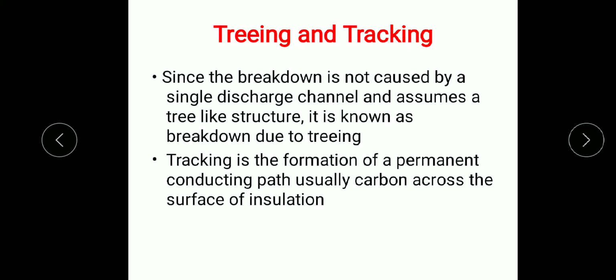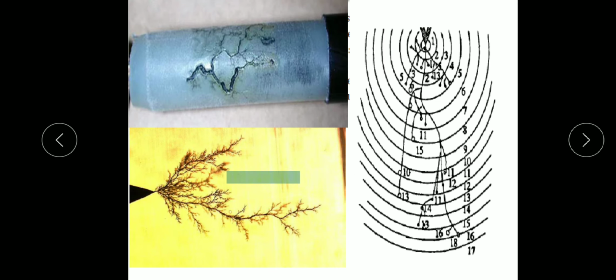The next is treeing and tracking. Since the breakdown is not caused by a single discharge channel and assumes a tree-like structure, it is known as breakdown due to treeing. And tracking is the formation of a permanent conducting path, usually carbon, across the surface of insulation. You can have a look at the picture, then you will understand that concept. This is what treeing is.